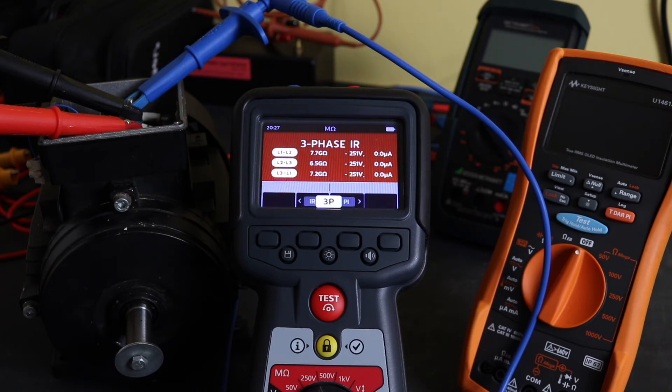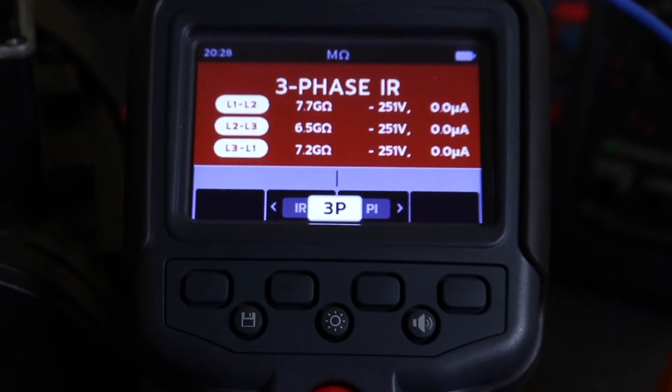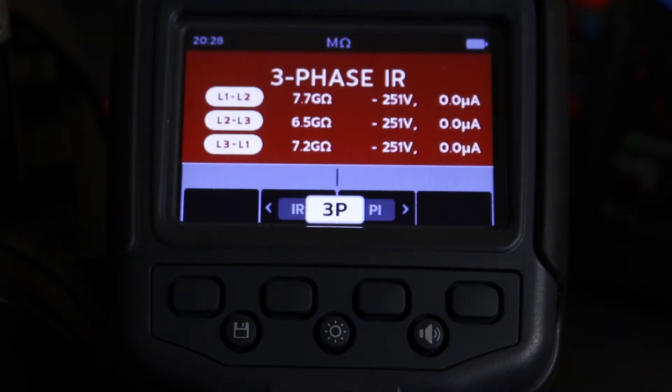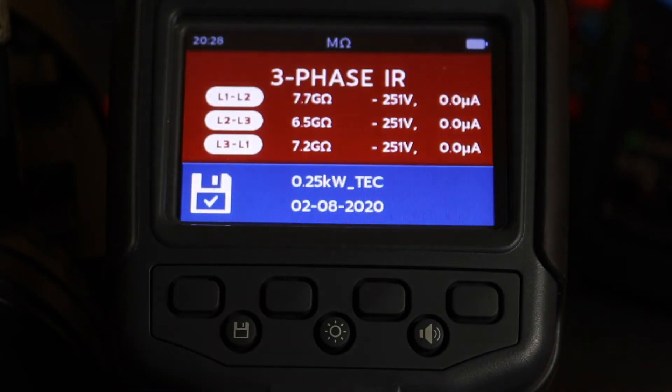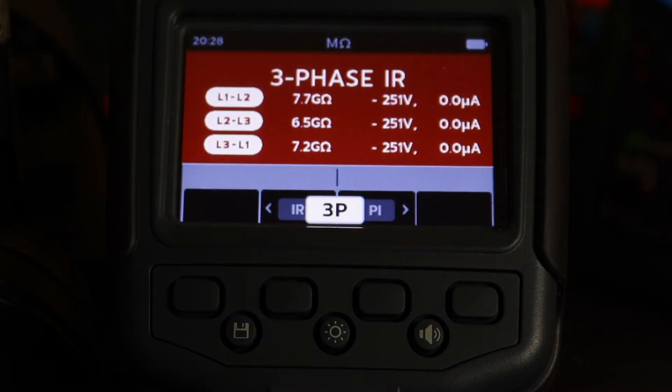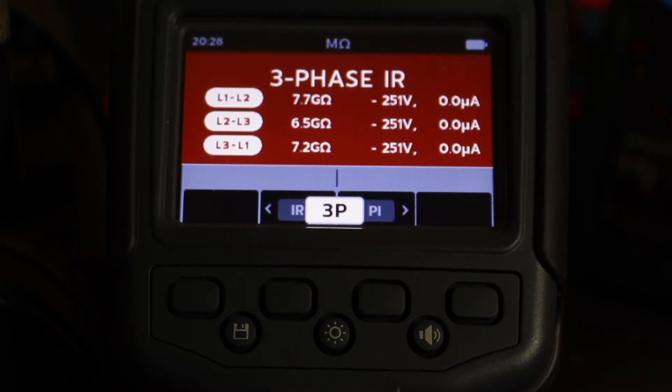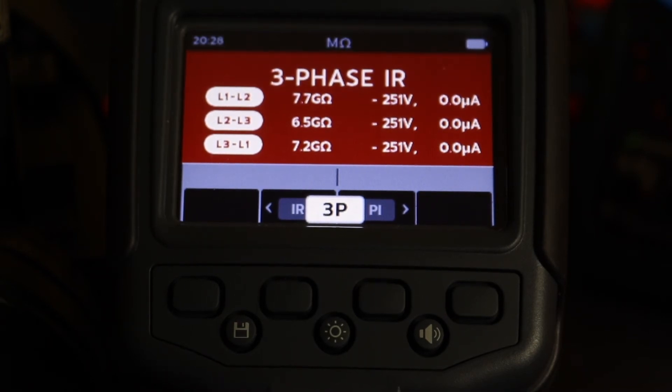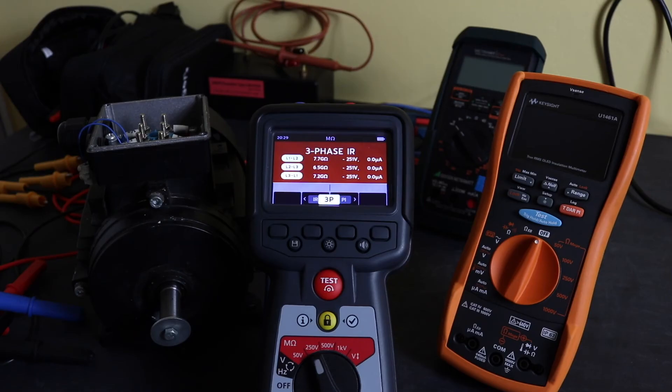There you go. That's the result done. So it gives you quite a nice screenshot at the end. Let's zoom into him a little bit, hopefully. Yeah, so it gives me a nice little summary of the test there. Obviously I can save that. And it gives me the resistance reading between each of the phases, test voltage, and the current, which it doesn't have enough resolution to display the current. So that's that test completed.